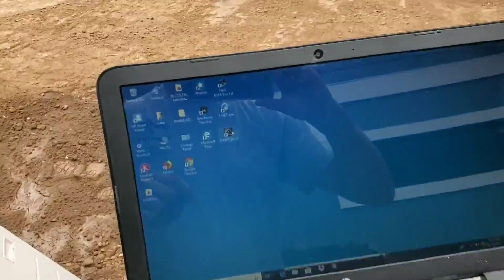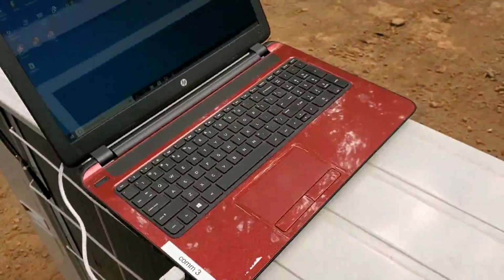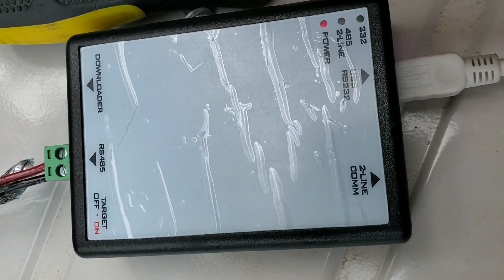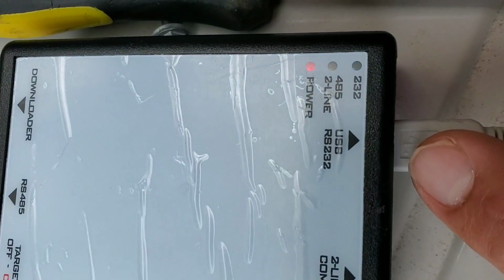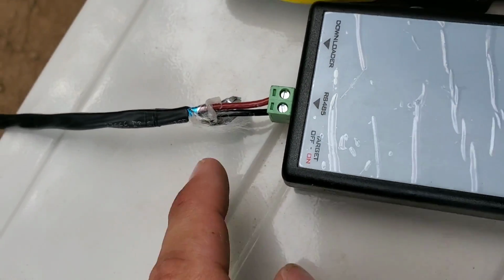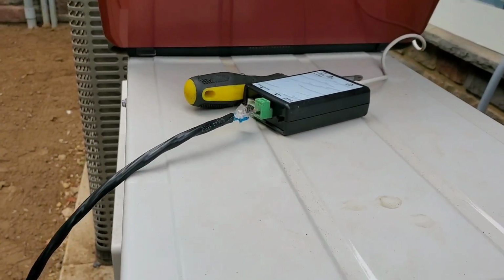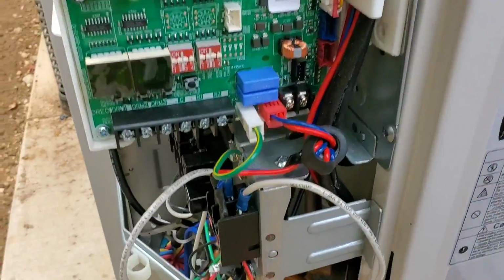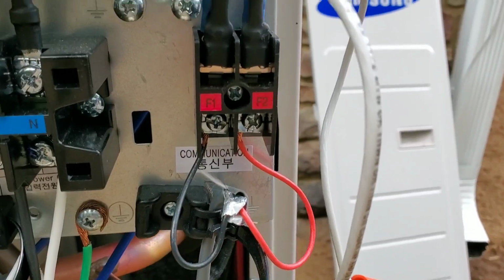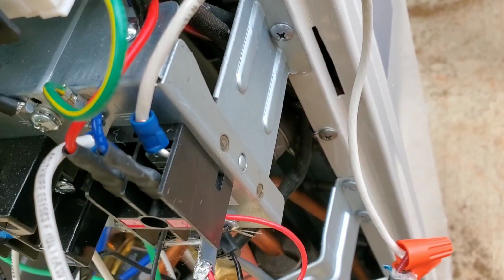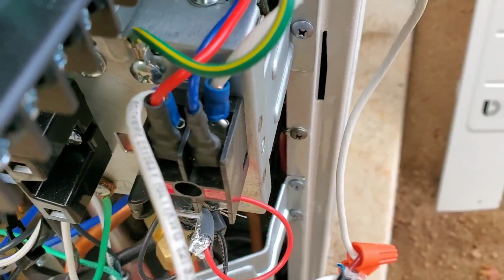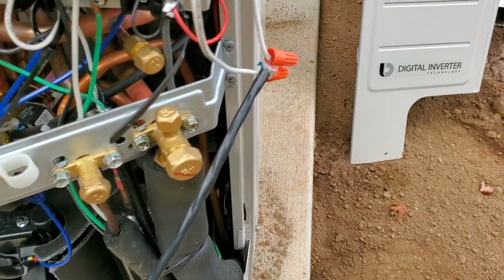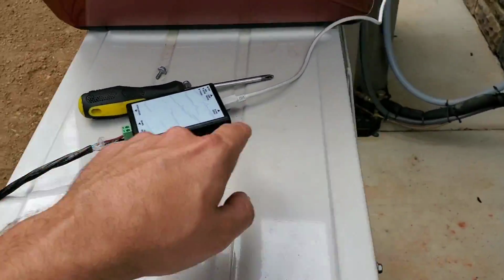A quick rundown. Right here on the computer is SNet Pro 2. This is the computer, and on COM3 I've got my USB wire and then my SNet converter box. This is the converter box. I've got the USB plugged into this terminal here, USB to RS232, and on the other side I have the RS485. These two wires run from that box into the F1 and F2 communication terminals. I've got a female spade and another female spade, two female spades, and those connect to the wire. That wire is coiled up right there, goes into my box, and back to my computer.